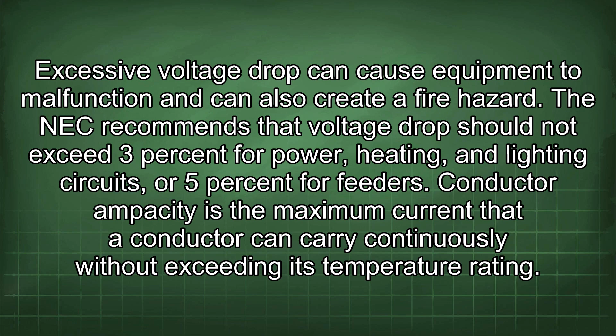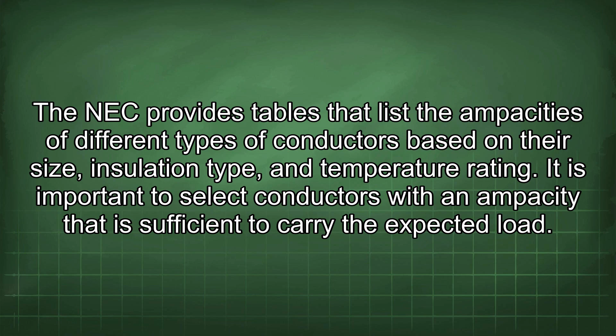Conductor ampacity is the maximum current that a conductor can carry continuously without exceeding its temperature rating. The NEC provides tables that list the ampacities of different types of conductors based on their size, insulation type, and temperature rating. It is important to select conductors with an ampacity sufficient to carry the expected load.